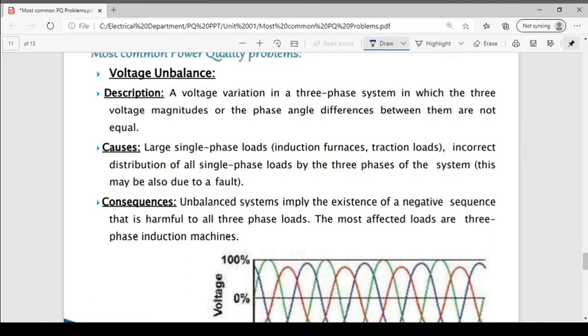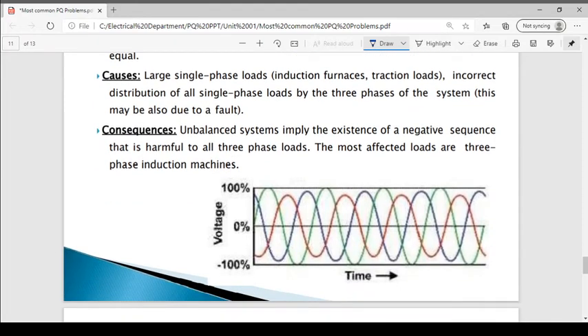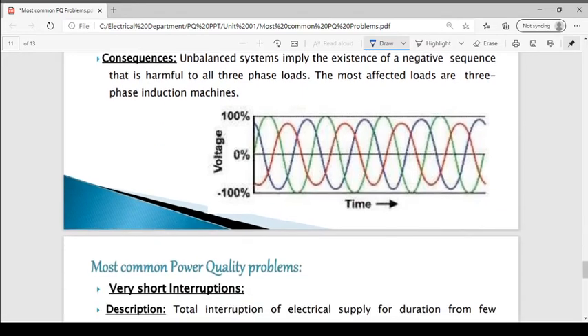So what will result from the voltage unbalance? What are the consequences? See, an unbalanced system implies the existence of the negative sequence, which is harmful to all the three-phase loads. And the most affected loads are the three-phase induction machines.